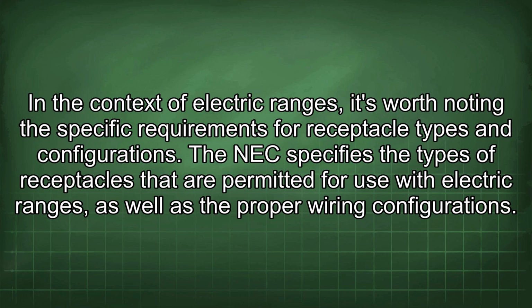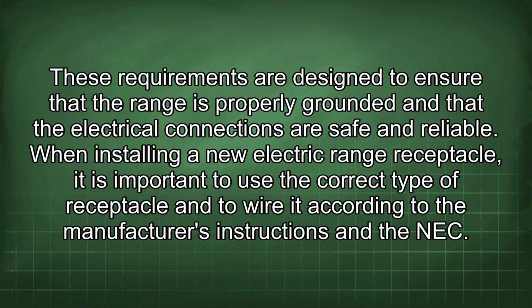In the context of electric ranges, it's worth noting the specific requirements for receptacle types and configurations. The NEC specifies the types of receptacles that are permitted for use with electric ranges, as well as the proper wiring configurations. These requirements are designed to ensure that the range is properly grounded and that the electrical connections are safe and reliable. When installing a new electric range receptacle, it is important to use the correct type of receptacle and to wire it according to the manufacturer's instructions and the NEC.